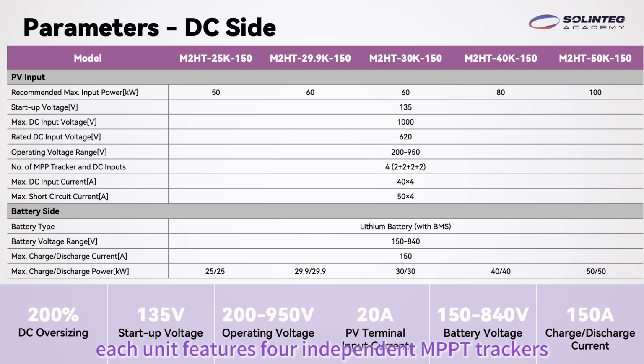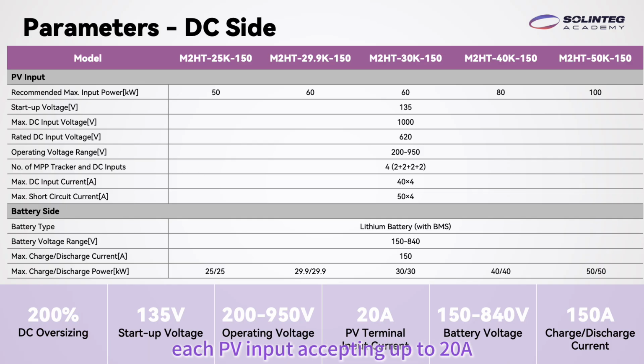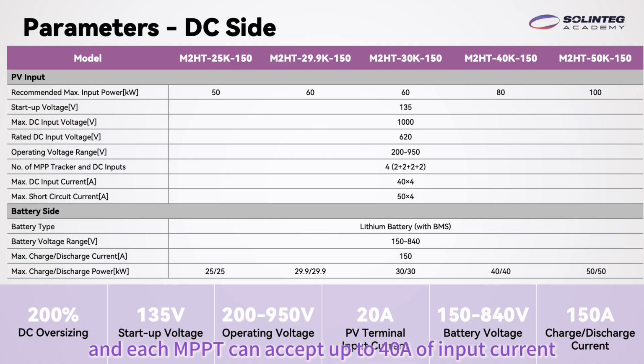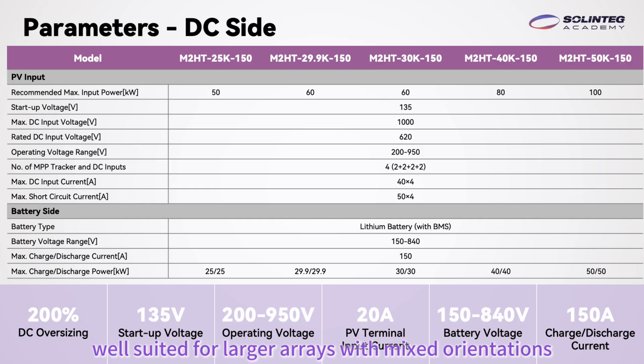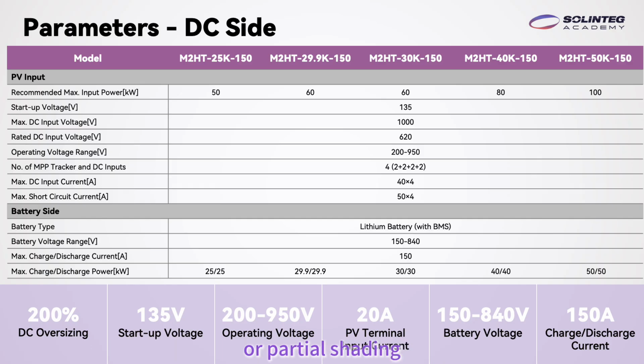Each unit features 4 independent MPPT trackers, each PV input accepting up to 20 amps, and each MPPT can accept up to 40 amps of input current, well suited for larger arrays with mixed orientations or partial shading. On the battery side, the M2HT supports lithium batteries with BMS across a voltage range of 150 to 840 volts and delivers up to 150 amps of charge and discharge current across all models. Maximum charge and discharge power matches the inverter rating.